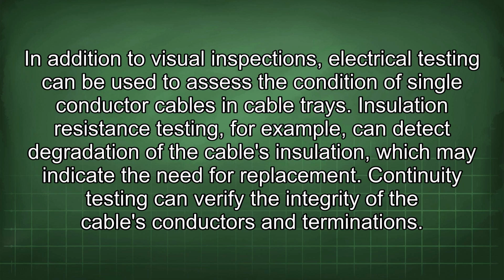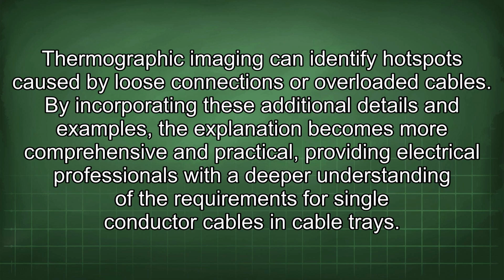Insulation resistance testing, for example, can detect degradation of the cable's insulation, which may indicate the need for replacement. Continuity testing can verify the integrity of the cable's conductors and terminations. Thermographic imaging can identify hotspots caused by loose connections or overloaded cables.